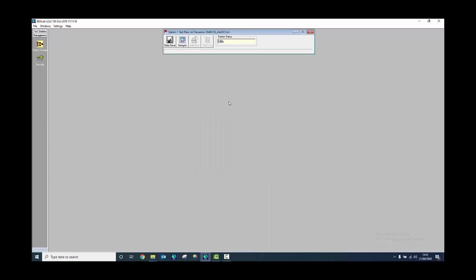And for this test, we'll use the single directory. I'll click Next. We'll use the linear saving type, .gds format of the file, and one data saving interval of 1 second. We'll tick the box to save the calculated data, which will save the parameters calculated based on the initial sample size, like strain and stress. Next. In here, we'll specify the location of the file and the name. And we can click OK. Then we can move on to the sample setup.